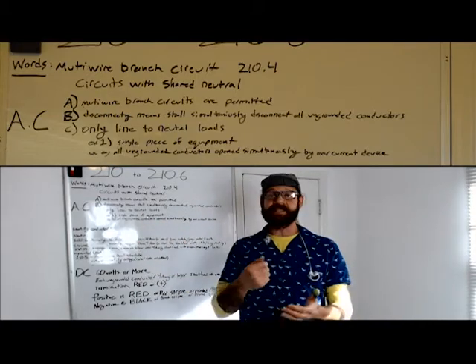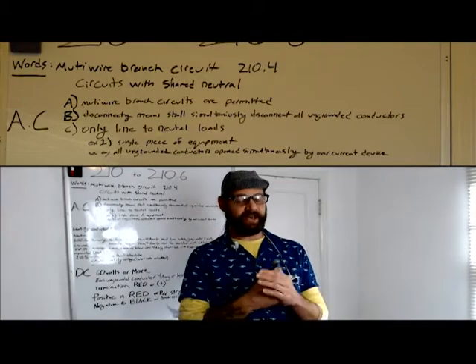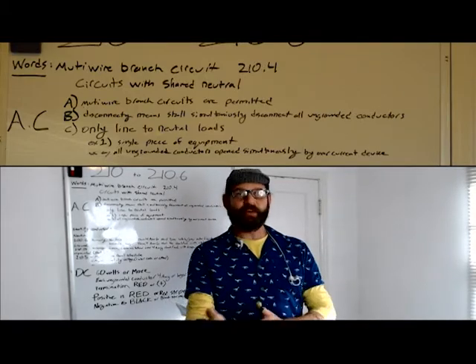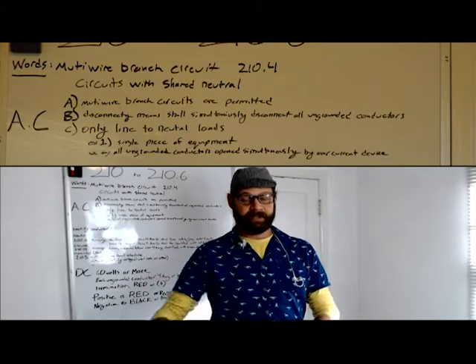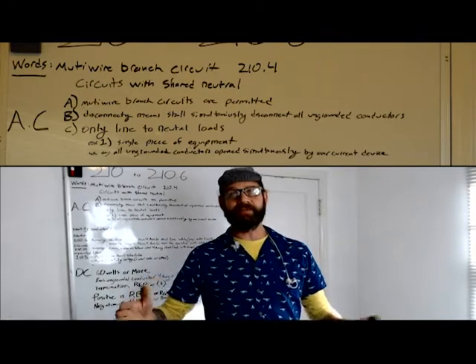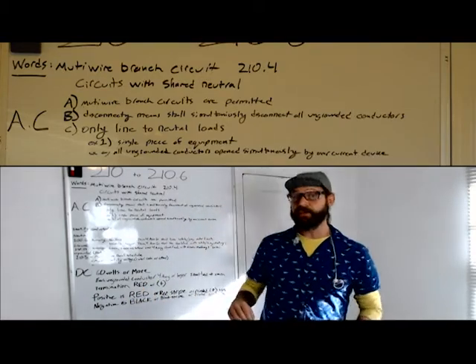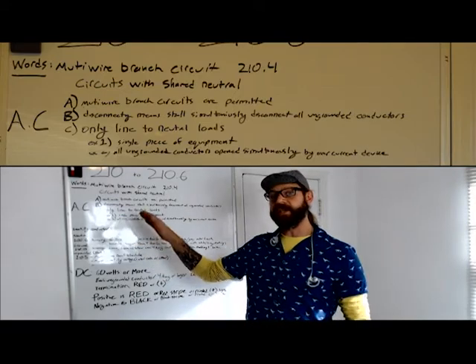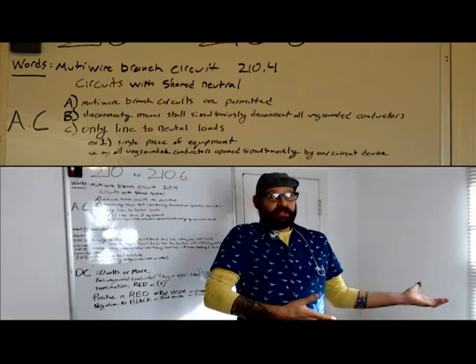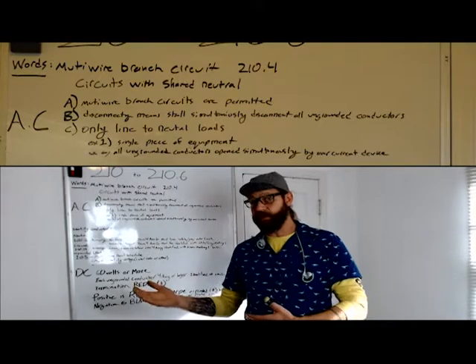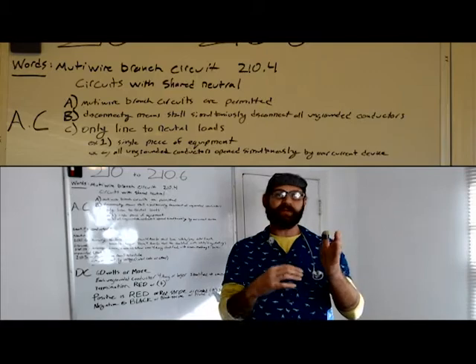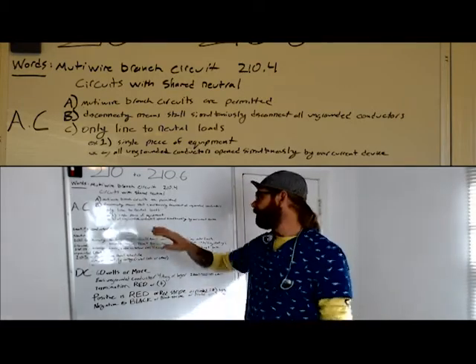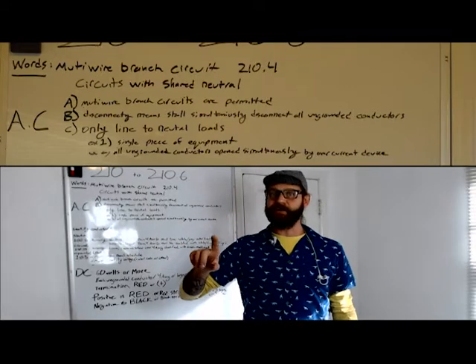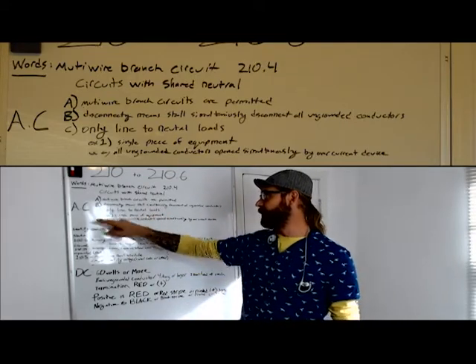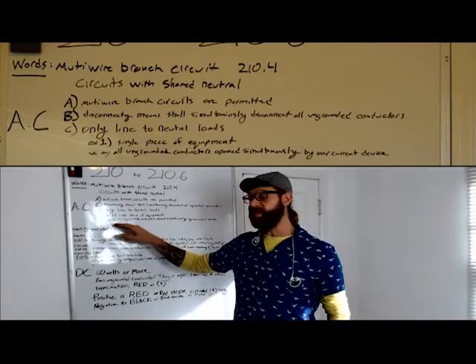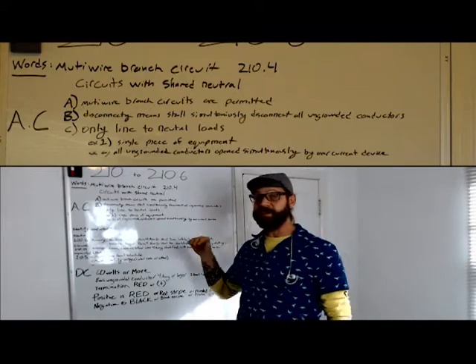The first exception is that it's a single piece of equipment. If you have a dishwasher, or industrial washing machines, industrial like the Hobart machines, a couple of water heaters, they all do this. If it requires 208 and 120 volts, like the dishwasher heater is 208 volts and all the control unit is 120 volts, it's in one plug. It's 208, 120, 2 hots, neutral, 2-pole breaker, totally good. It supplies 2 different voltages. It's a single piece of equipment. That's exception 1. So exception 2 is, of course, that all ungrounded conductors are opened simultaneously by the overcurrent device.